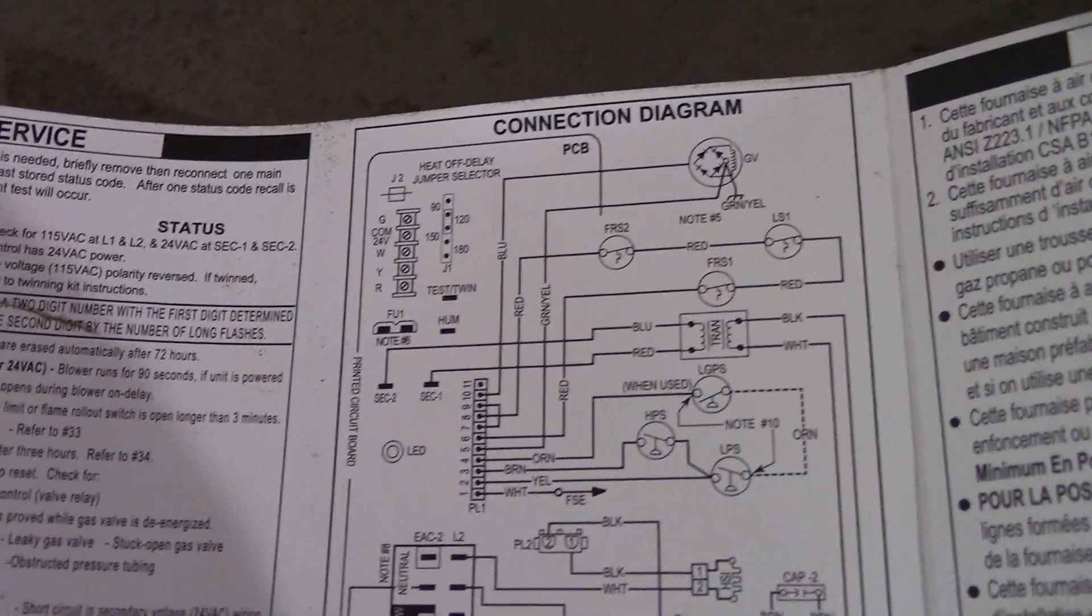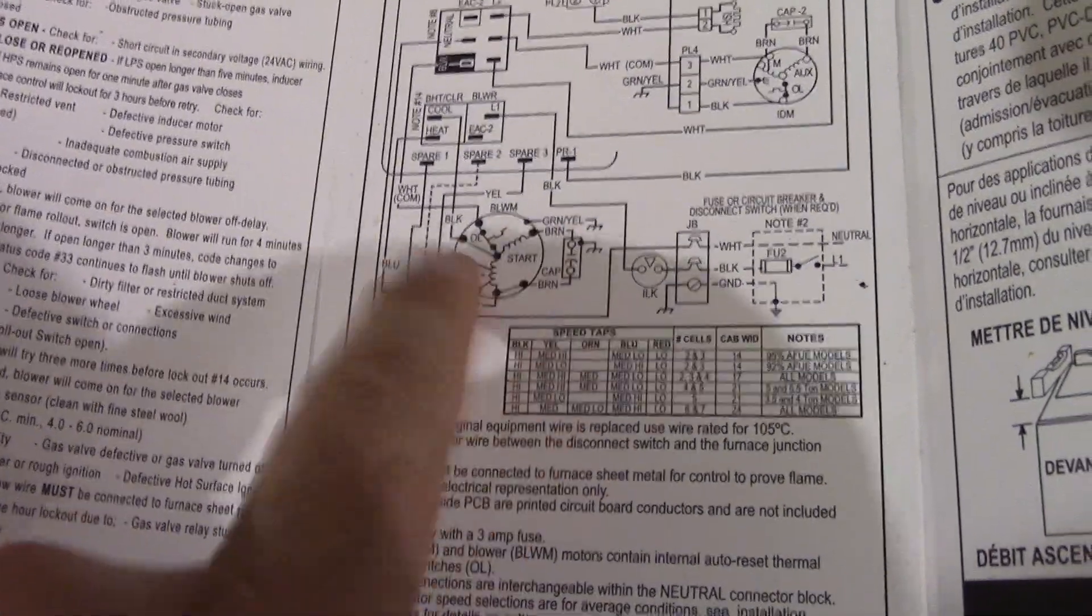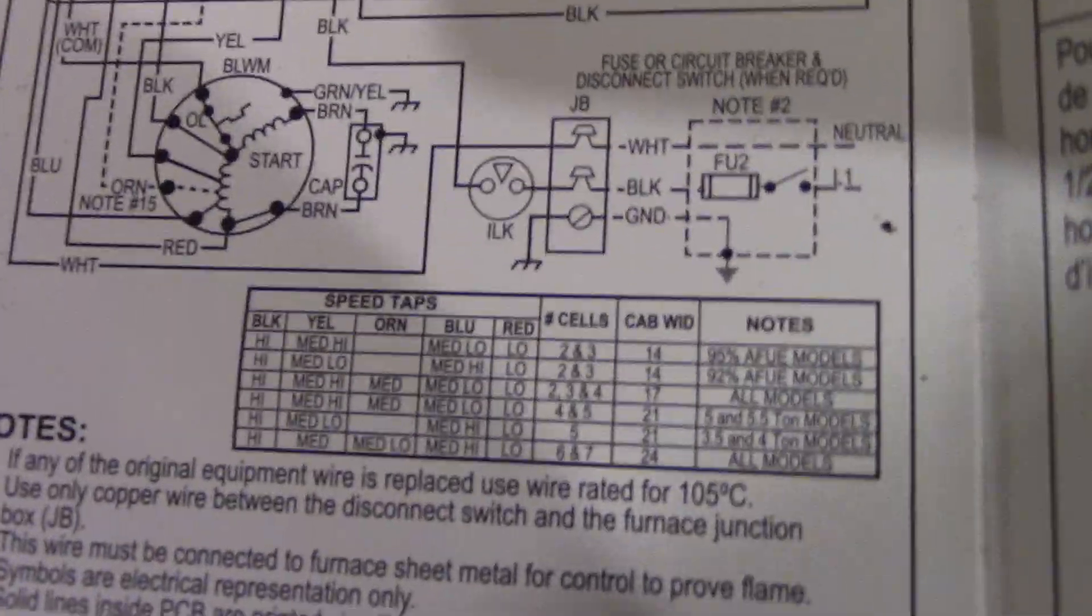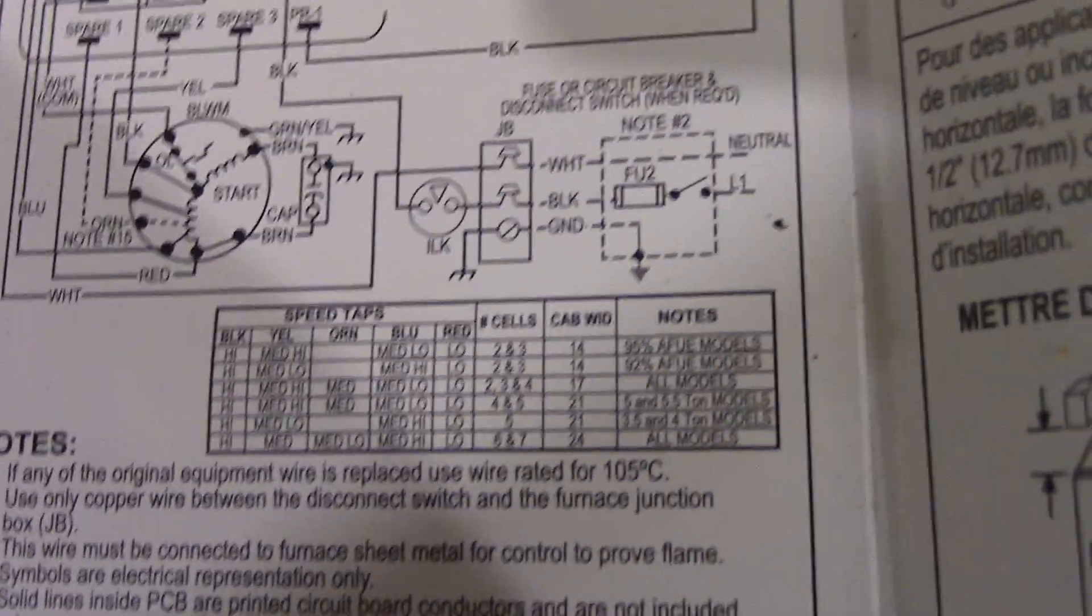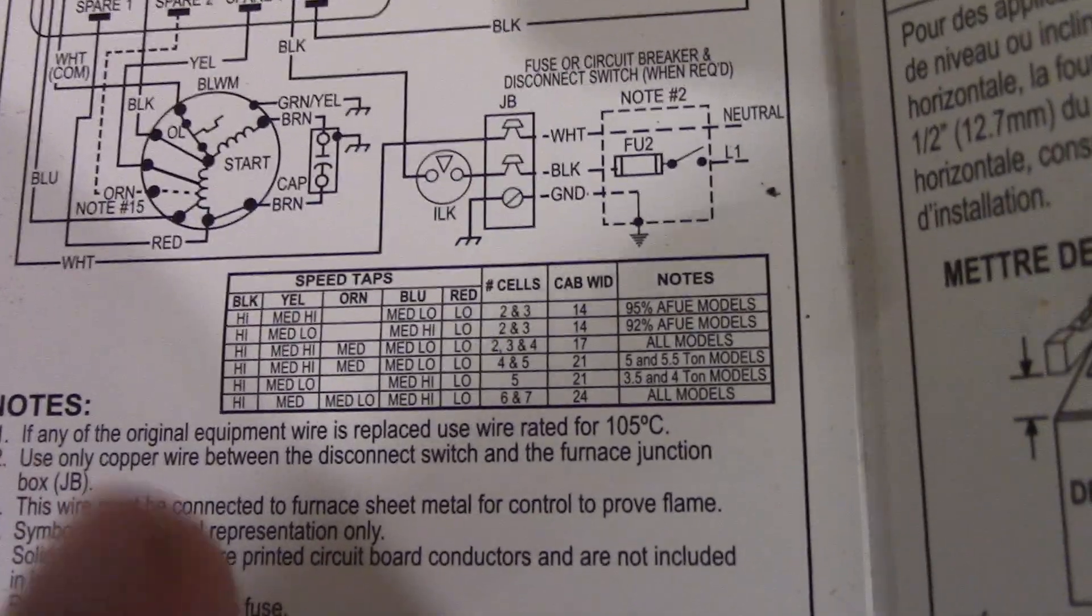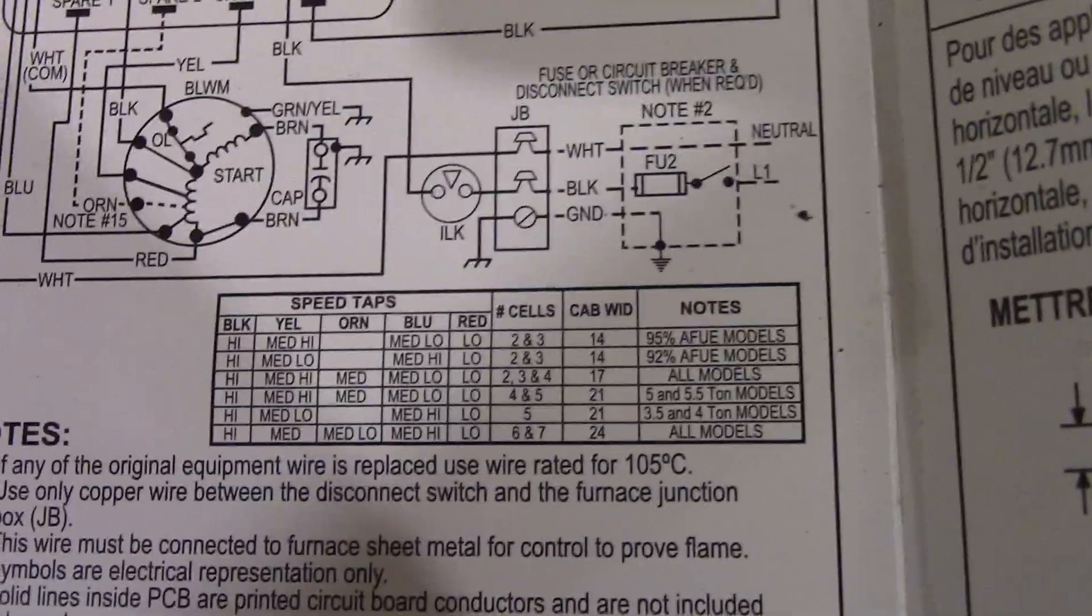Here's the wiring diagram. Sometimes you may have the speeds indicated on this diagram itself, but in my case here, you can see I have a chart. As you can see, pretty much for all models, black is high and red is low. That doesn't change. But what's in between is the ones that change. Here's how I figured mine out.